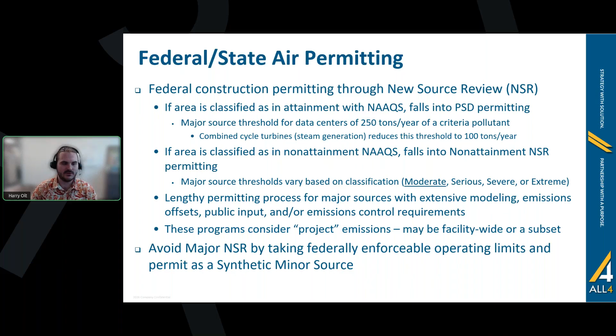Data centers often avoid major NSR and the associated longer permitting processes by taking federally enforceable limits on operating time or fuel consumption to intentionally reduce potential emissions below the major source thresholds, and therefore be permitted as a synthetic minor source.